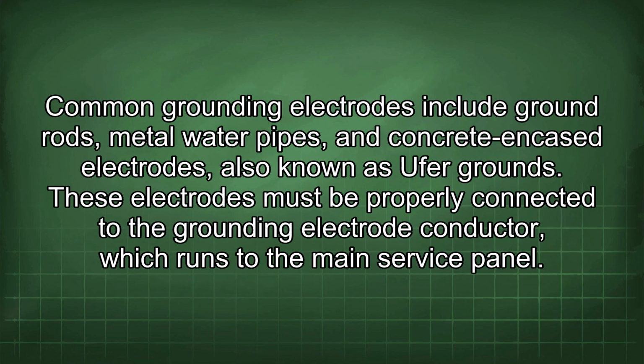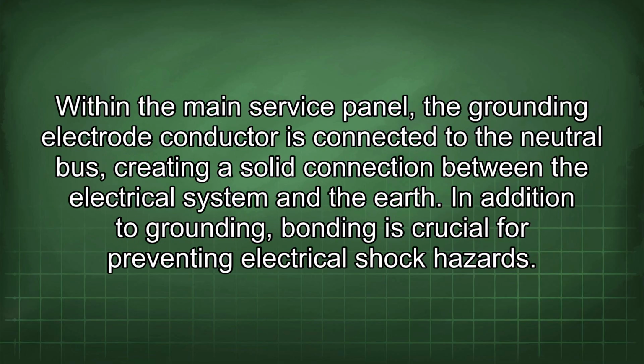Common grounding electrodes include ground rods, metal water pipes, and concrete encased electrodes, also known as UFER grounds. These electrodes must be properly connected to the grounding electrode conductor, which runs to the main service panel. Within the main service panel, the grounding electrode conductor is connected to the neutral bus, creating a solid connection between the electrical system and the earth.